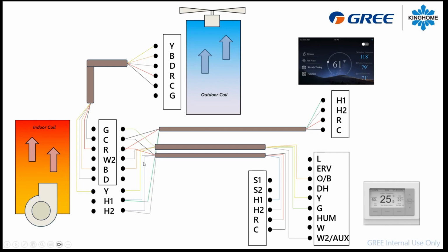And this is much easier to work with when all your connections are inside the air handler. So basically, you will have to run 2 different wires from the mechanical room to the air handler and just use the one from the main floor directly inside the air handler also. You can label your wire. This is also a great way to help you on a service call when all the wires are labeled, so you know which one goes where.